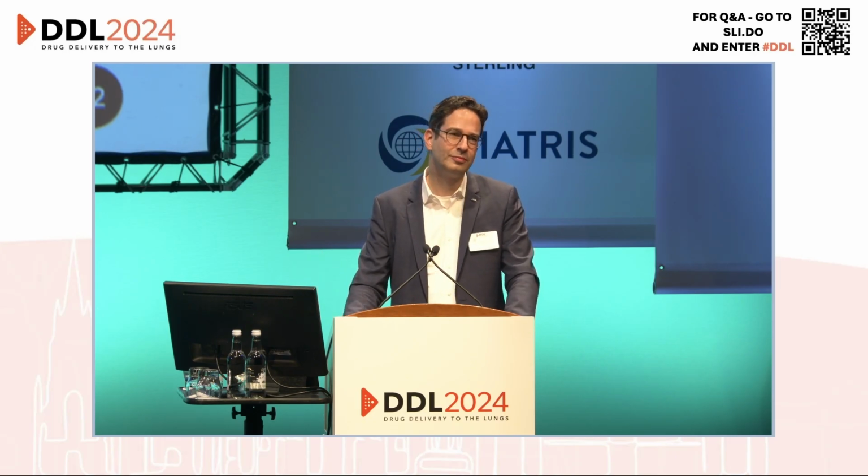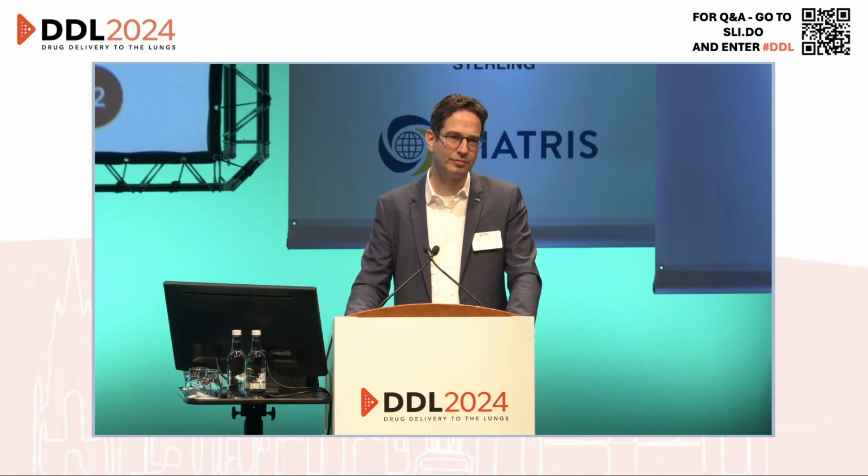But I think that they did laser diffraction, and those data show excellent one-to-one correlation between the modeling and the laser diffraction data. But the laser diffraction data is like twice the size of what we know comes out of soft mist. So there's something kind of weird in their actual measurement as well. That's probably good if people know that. Yeah.